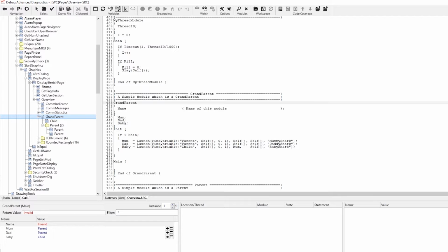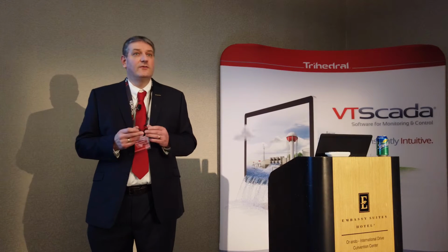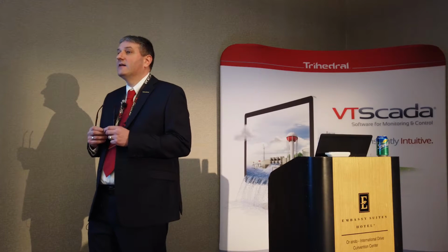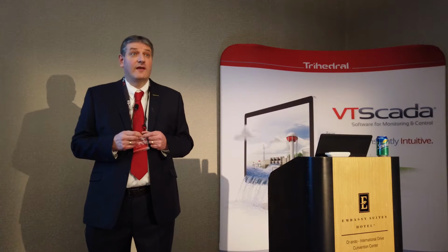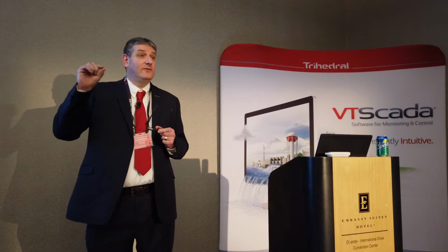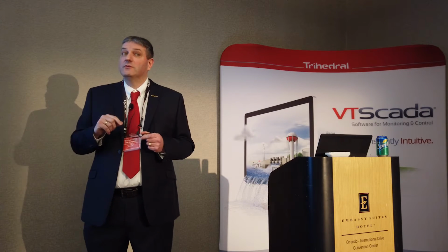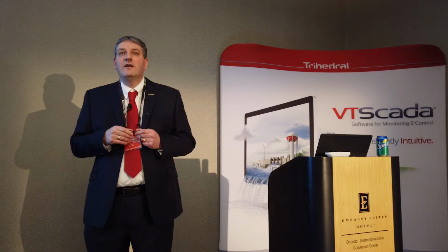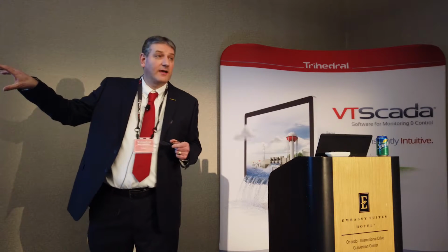Okay. If I click on the Instance tab, there are no instance variables. Instance variables are very rarely used, but just to cover off for completeness, when VTScada creates a child tag, for example, when you create a child tag, a reference is temporarily added to the parent of that module, and only that instance of the module, so not for every instance of the module. So if you were debugging instance variables, you would see them listed there. It's not used very often, certainly in day-to-day use of VTScada.